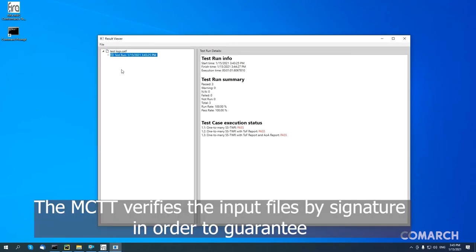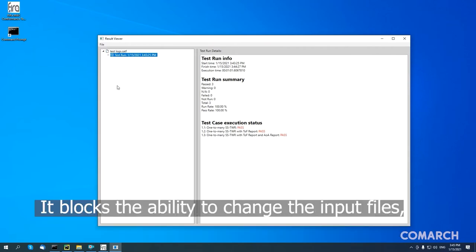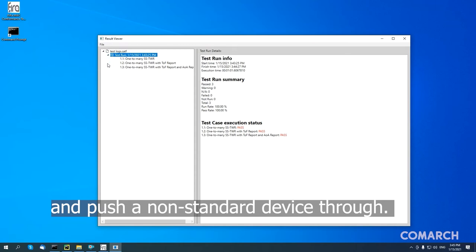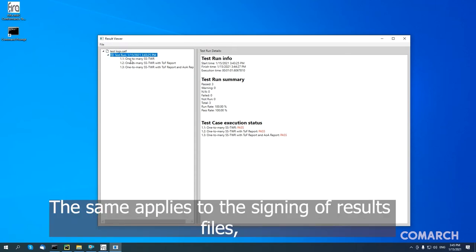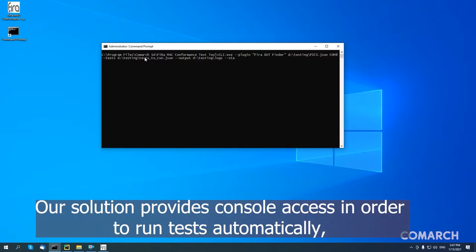The MCTT verifies the input files by signature in order to guarantee that the tests are not corrupted. It blocks the ability to change the input files, thanks to which it is not possible to modify a test and push a non-standard device through. The same applies to the signing of results files — there is no possibility to falsify them.